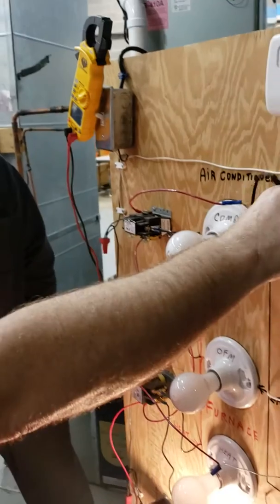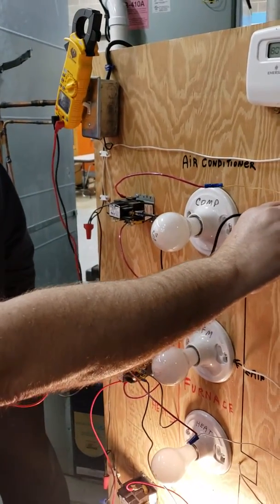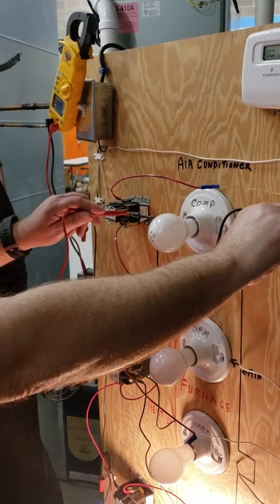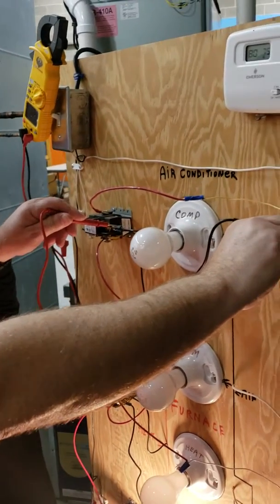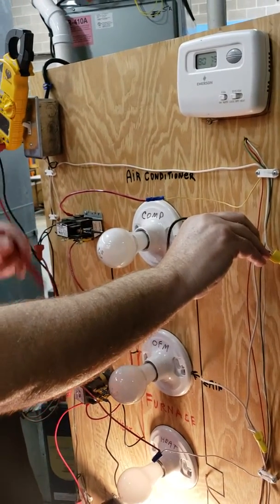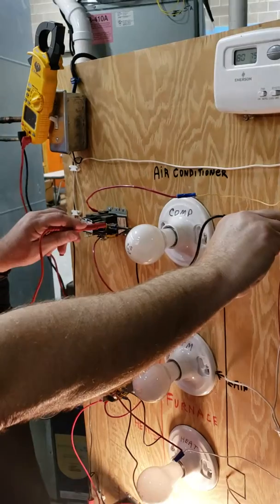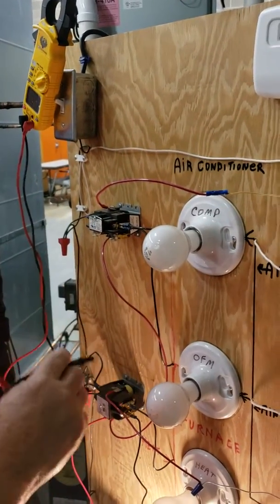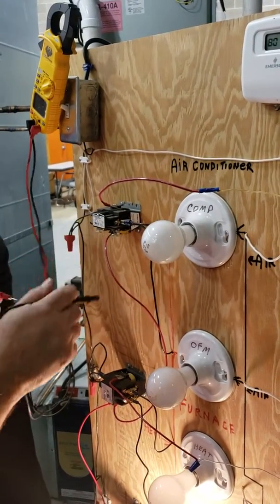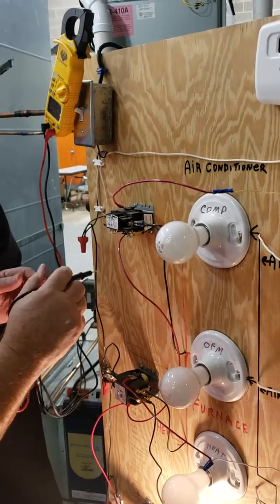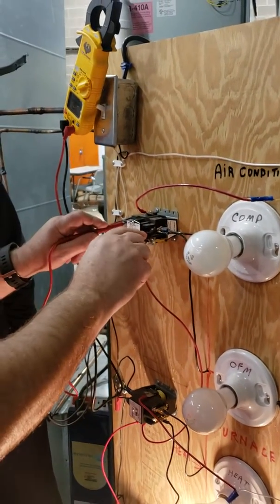The next thing I'm going to do is I'm going to check what? Load. My load. Do I have anything? No. So I don't expect the compressor and the fan to run, do I? Okay. Well, is it supposed to? So what can interrupt that path? Well, my contactor can interrupt that path, right? So let me check across that.